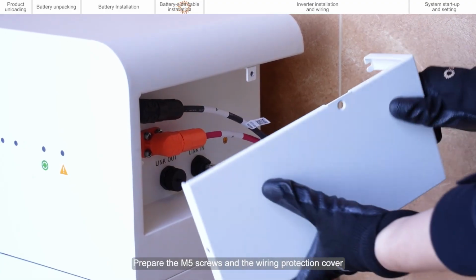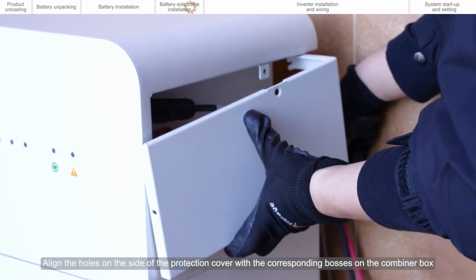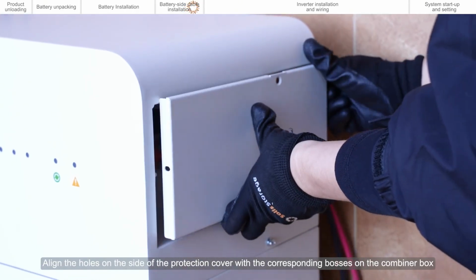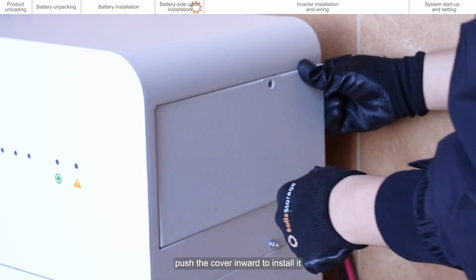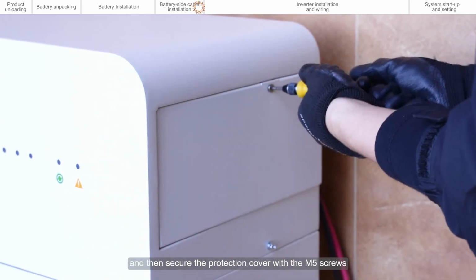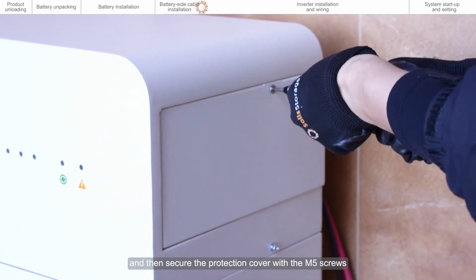Prepare the M5 screws and the wiring protection cover. Align the holes on the side of the protection cover with the corresponding bosses on the combiner box. Push the cover inward to install it, and then secure the protection cover with the M5 screws.